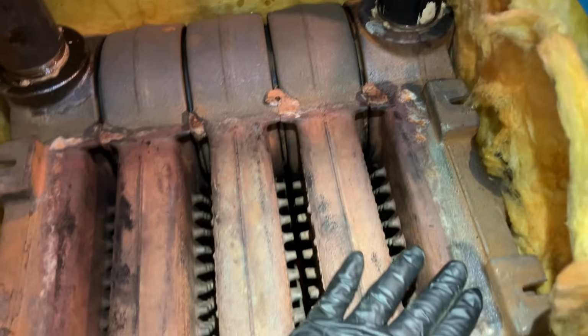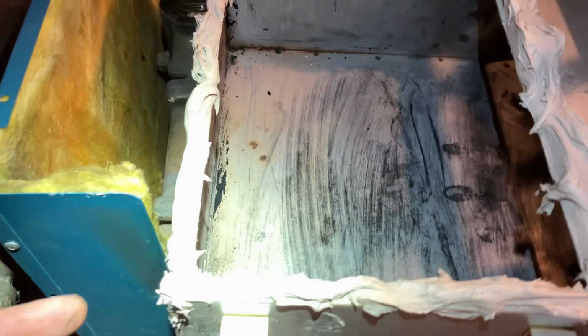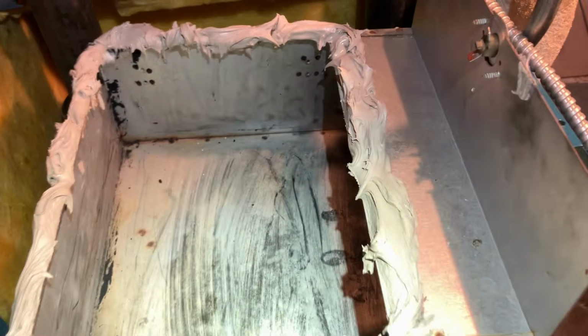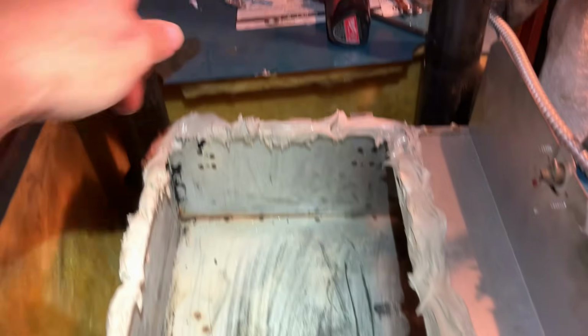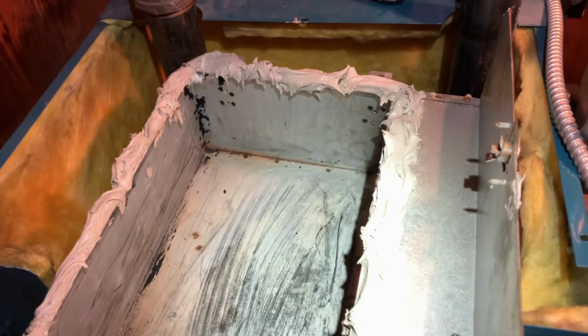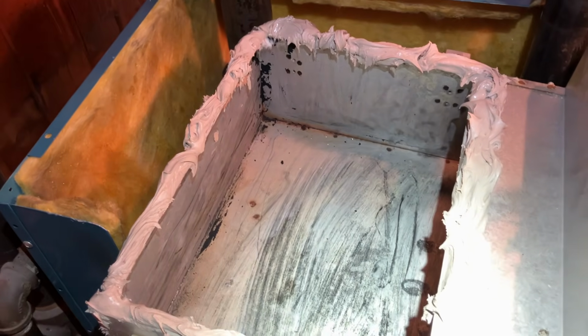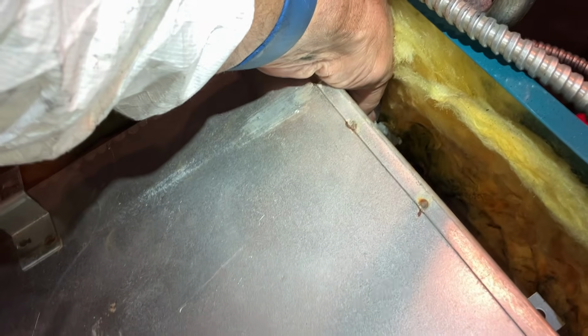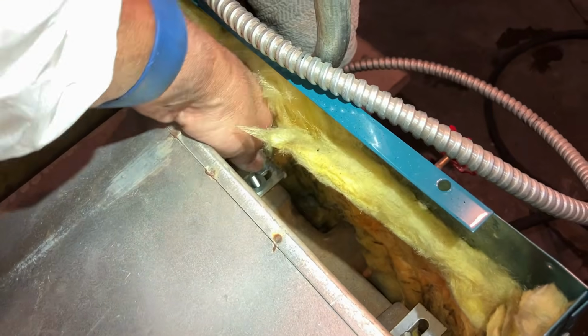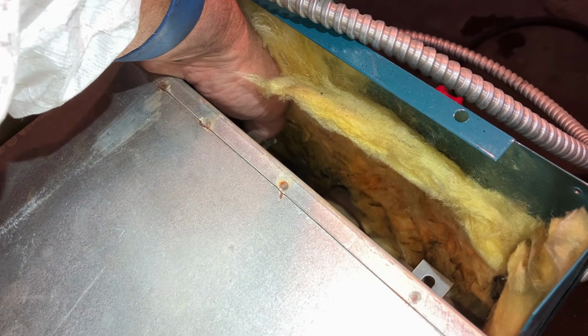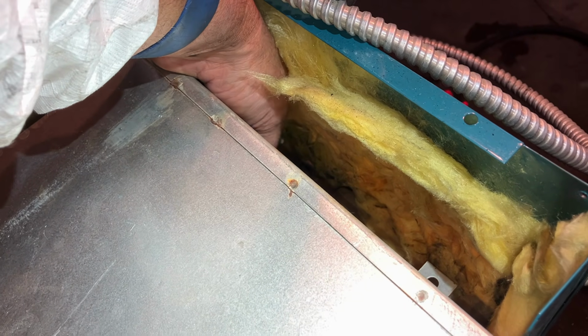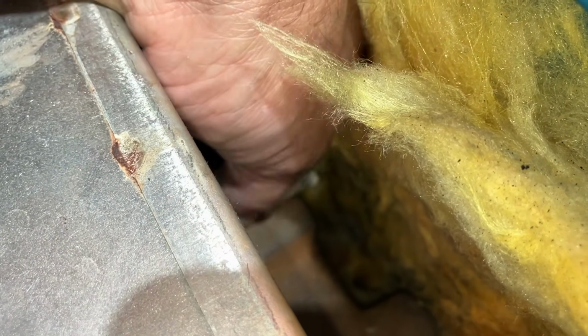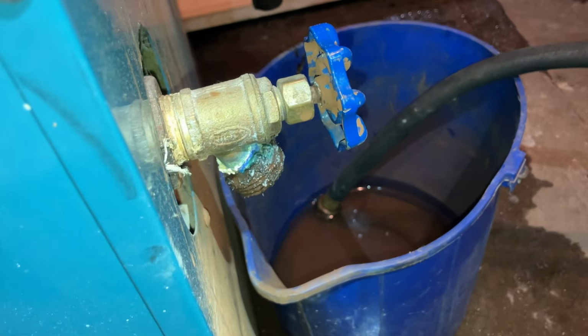All right. Let's go. All right, so wearing some gloves, I applied the high temperature furnace cement around the perimeter of the draft hood here. And let me set those 2 bolts on this hard, difficult to access side, and set this internal draft hood. Okay. It looks like we are centered. So before I lose these bolts, let's get the washers on there and the little nuts. You can also remove the side panel here to make access easier. That's dripping. Yeah, we're gonna need to replace that.